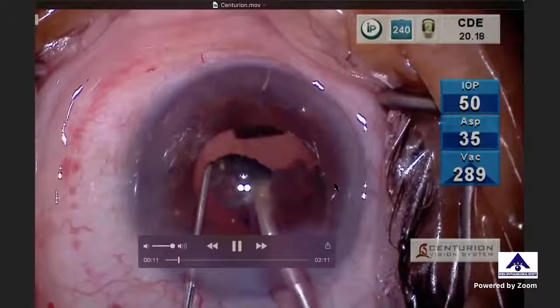Share my screen. One minute. Irrigation pressure and vacuum, and compensates for the pressure loss by squeezing the BSS bag more to help maintain the surgeon-selected IOP. This results in a more stable anterior chamber. With gravity fluidics, since the fluid source is static, the anterior chamber is less stable during cataract removal. Some surgeons use an air pump to achieve, for example, a bottle height of 95 centimeters of water. I think I started it twice. Let me start it again.